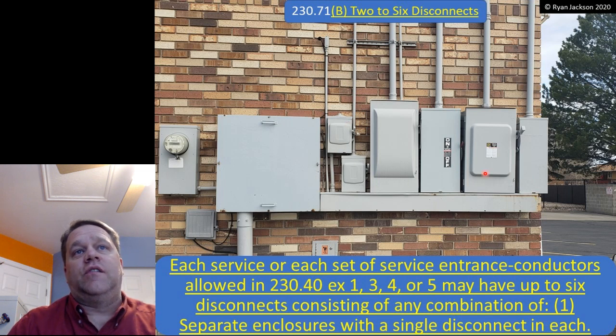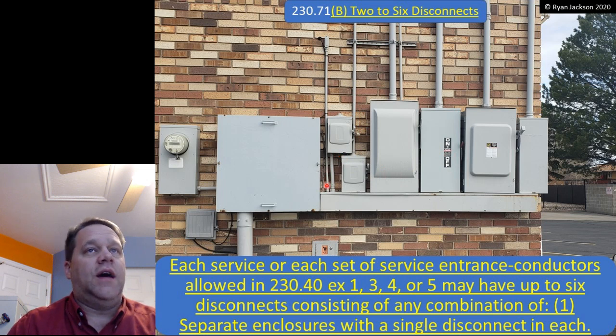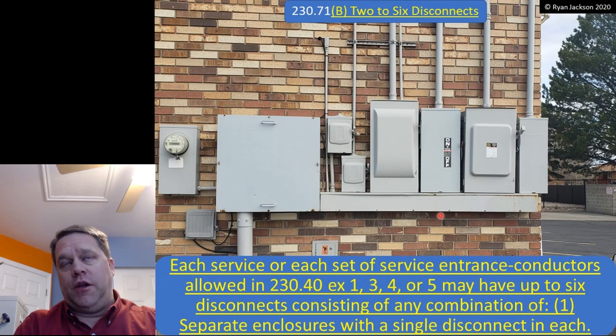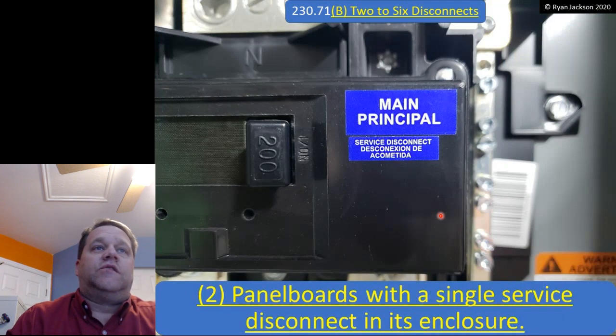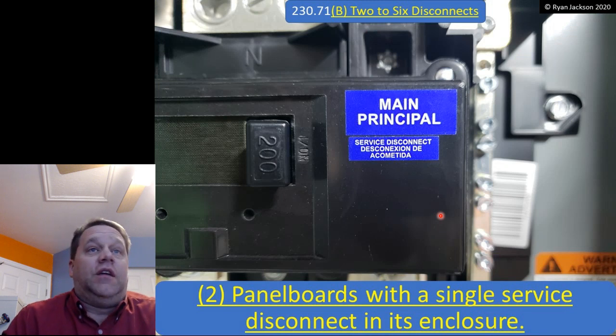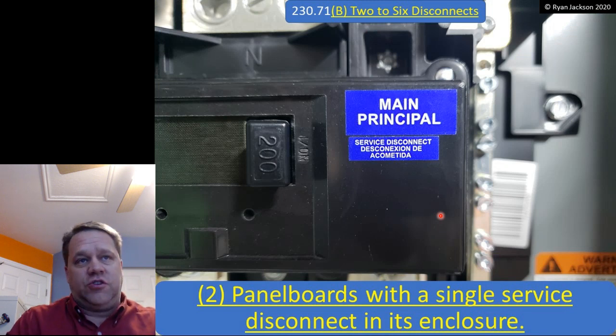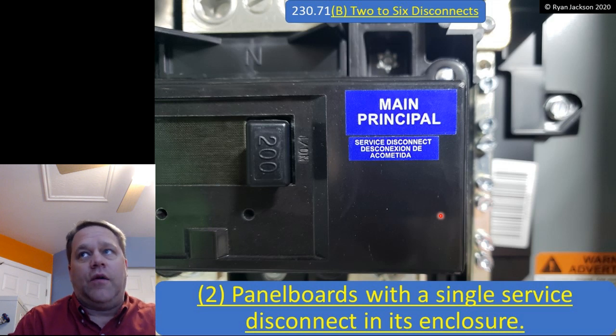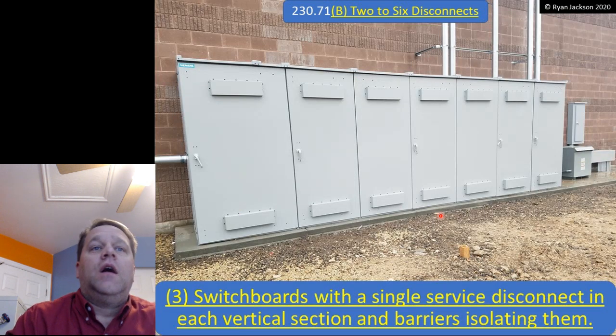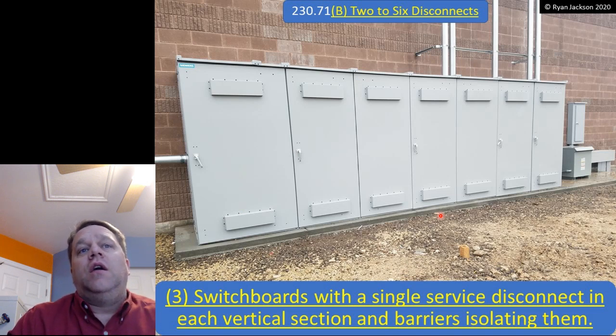I've got 6 disconnects, but I can't have more than 1 service disconnect per enclosure. So 6 enclosures, each with a maximum of 1 disconnect. That is still okay. Much more commonly, what we're going to find is a panel board with a single service disconnect in its enclosure. So a main breaker panel, that's your service disconnect. That is allowed. Or item 3, switchboards with a single service disconnect in each vertical section if there's barriers isolating those sections from each other.